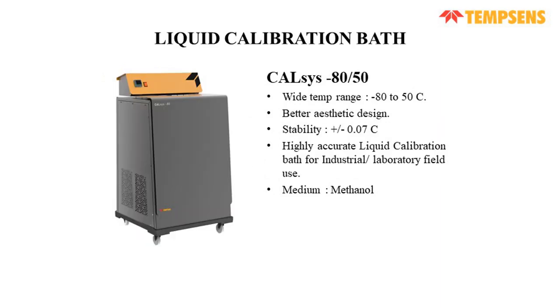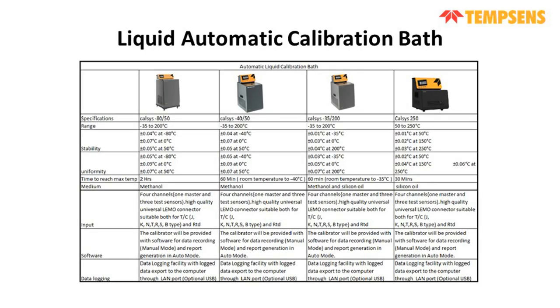Now this is the CALsys minus 80 to 50. The temperature range is minus 80 to 50 degrees centigrade with a much better aesthetic design, and the stability is plus minus 0.07 degrees centigrade. It is highly accurate and is used for laboratory purposes. The medium for this one is methanol. For above 0 degrees centigrade we will use water. All the liquid bath calibrators I have discussed till now are also available as automatic calibration baths, with a 5-inch screen that can also be customized. The specifications for the autocal models are given in the table.